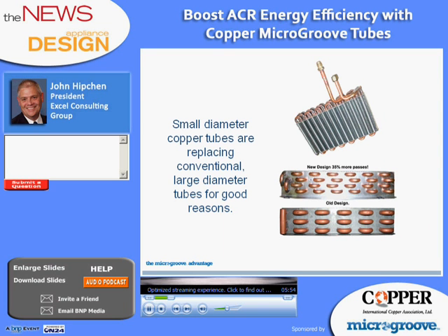Round tube, flat fin coils have been used for a very long time, in fact, more than 100 years. But this photo, which is right out of an Internet heat exchanger catalog, shows exactly the trend that we're going to discuss over the next hour. And that trend is towards smaller diameter copper tubes with special attention paid to the arrangement of the tubes.